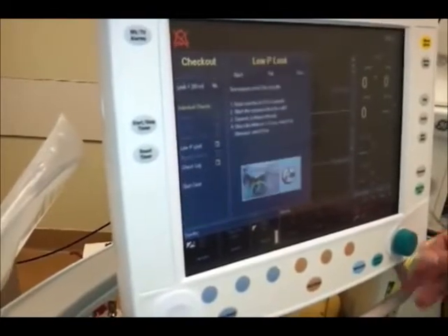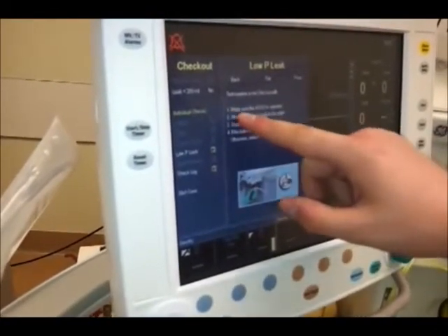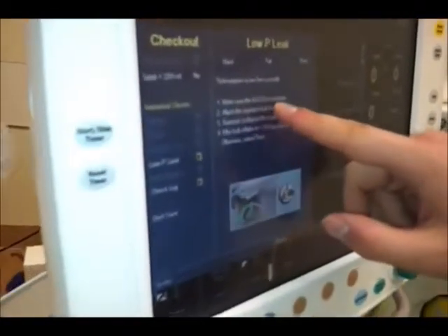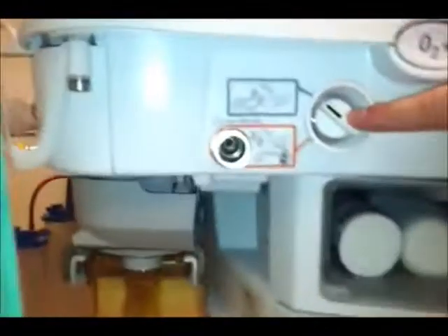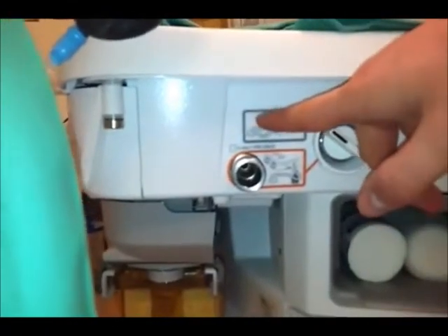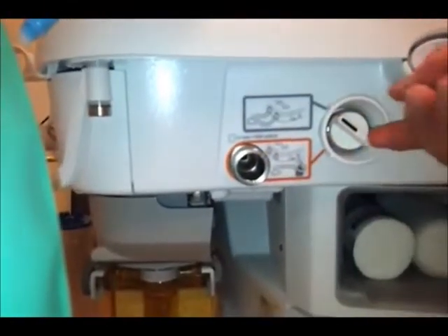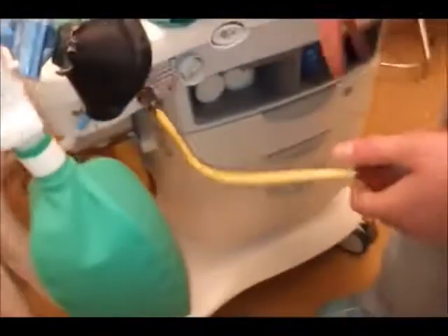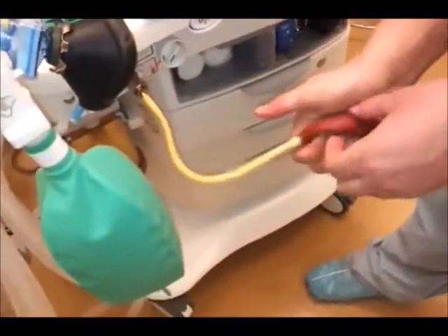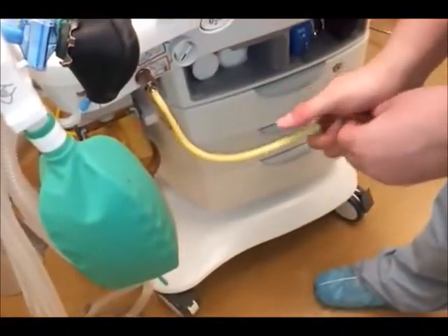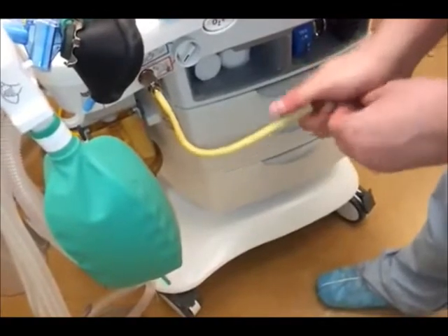So low pressure leak. You click on that. Each one of them has a list that tells you what to do. Make sure ACGO is selected. So the ACGO switch is right here. Most of the time it's set at circle, but for this you have to switch it down. Switch it down and plug in the bulb. Okay. And then basically you have to squeeze it a bunch of times until it sucks all the air out of the circuit.